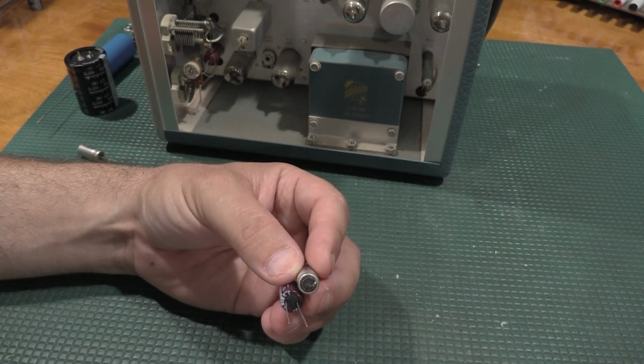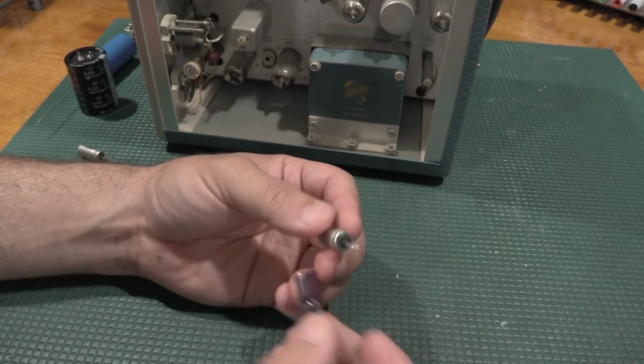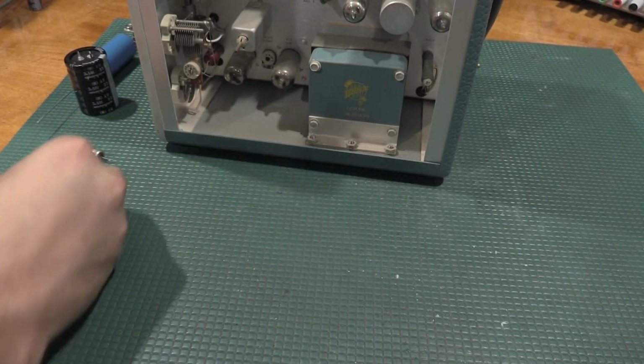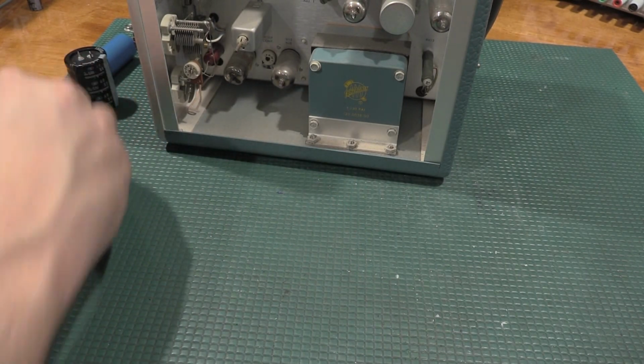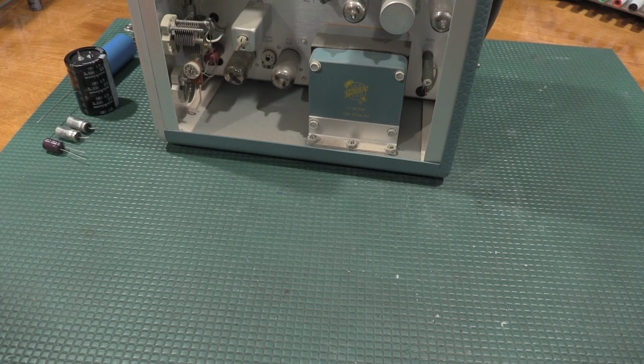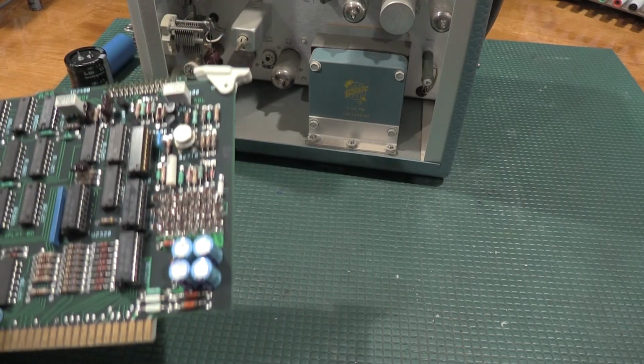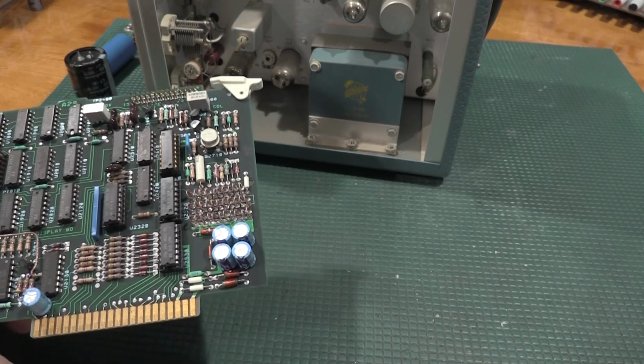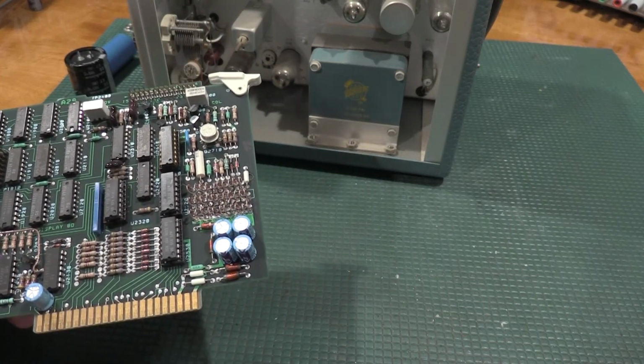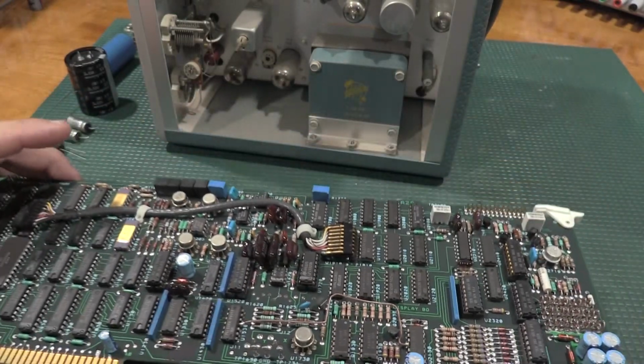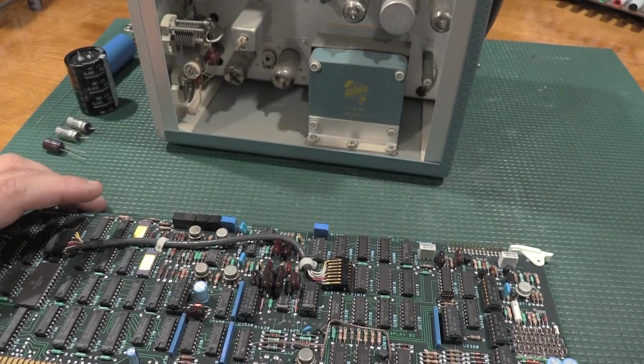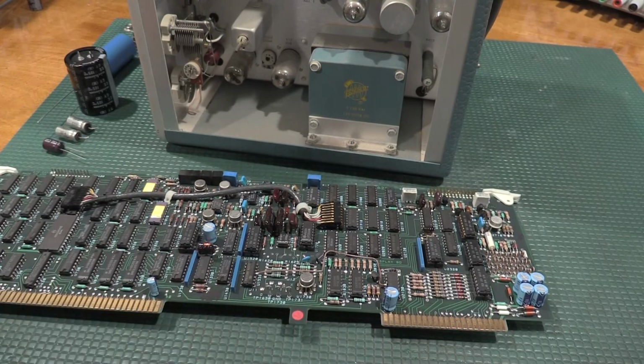But for the longevity of a repair, a capacitor is relatively inexpensive, so I just replace it, or I do what the customer tells me, but I do replace it. One of the reasons I recommend replacing the capacitors is that a lot of people send gear into the lab because they don't have the calibration gear necessary to check the device after it's been repaired. Now, if a capacitor is failing and the power rails change, that's going to throw off the calibration. It's going to need some adjustment.